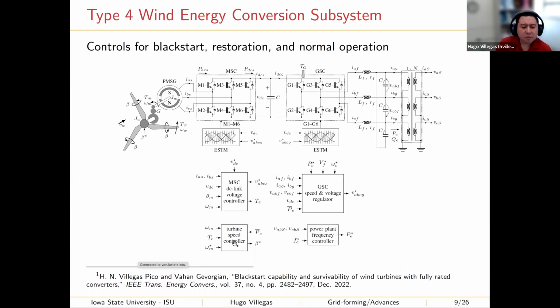Here one feature is that the turbine speed controller is connected to the grid side controller. If you see here, P_E bar. We needed that interconnection. If we recall a synchronous machine, it is connected through a shaft to the prime mover. So whenever there is a problem on the synchronous machine, for example, if it is overloaded, that overloading is transmitted through the shaft to the prime mover. Here we only have the interconnection of the DC link, but the DC link cannot inform that the grid side converter is transferring more power than the wind turbine can provide. In that case, it is necessary to have communication between the wind turbine's speed and the grid side converter, telling it, hey, I'm stalling, do something, reduce the amount of power.